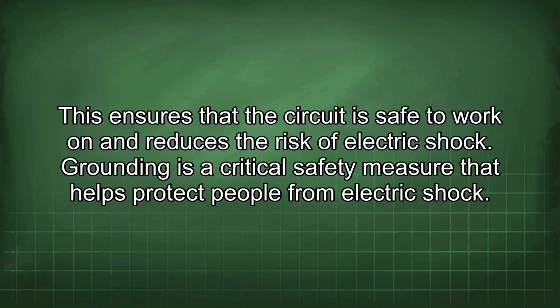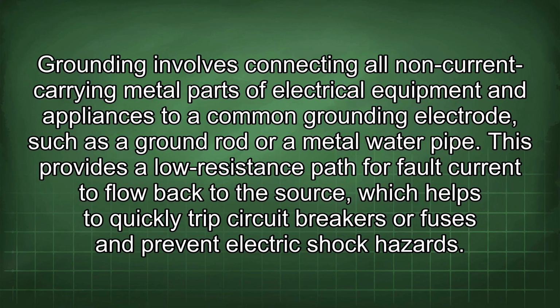Grounding is a critical safety measure that helps protect people from electric shock. Grounding involves connecting all non-current carrying metal parts of electrical equipment and appliances to a common grounding electrode, such as a ground rod or a metal water pipe. This provides a low resistance path for fault current to flow back to the source, which helps to quickly trip circuit breakers or fuses and prevent electric shock hazards.